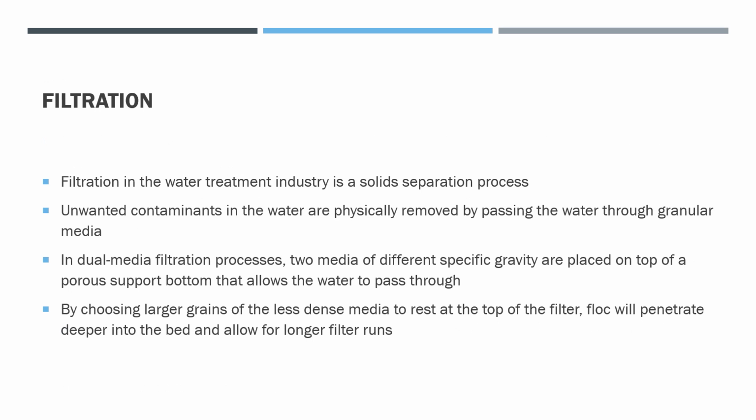Okay, moving on to filtration. Filtration in the water treatment industry, of course, is a solid separation process, just like sedimentation is. Again, unwanted contaminants in the water are going to be physically removed when we pass the water through, in this case, granular media filters.